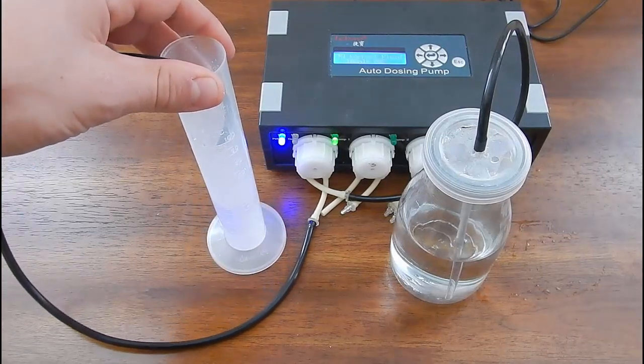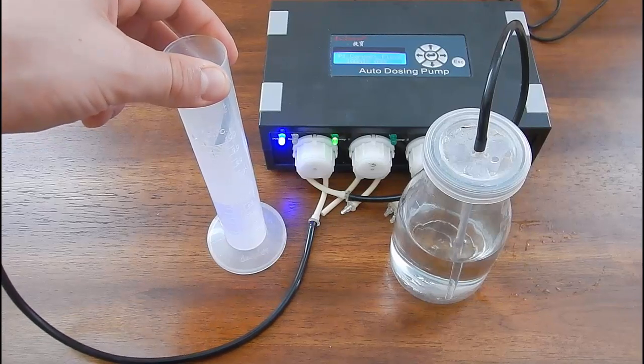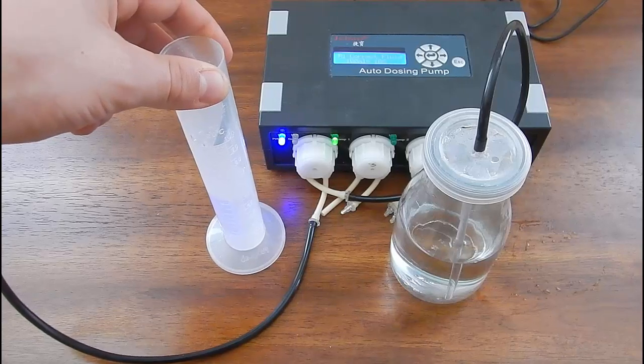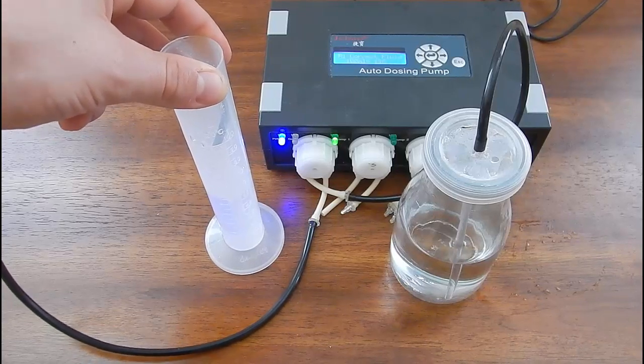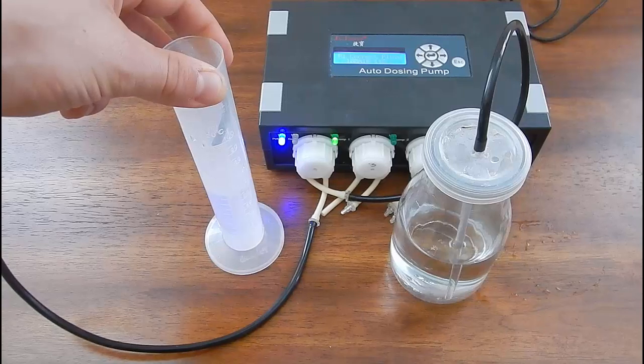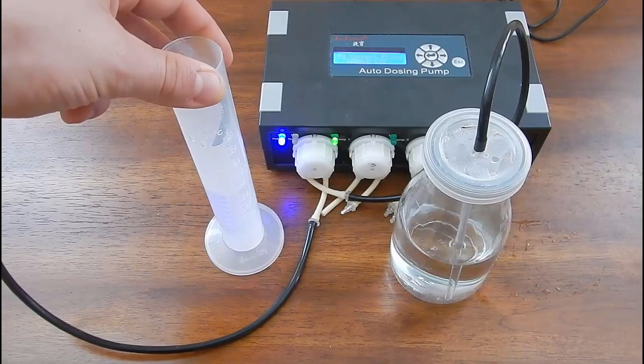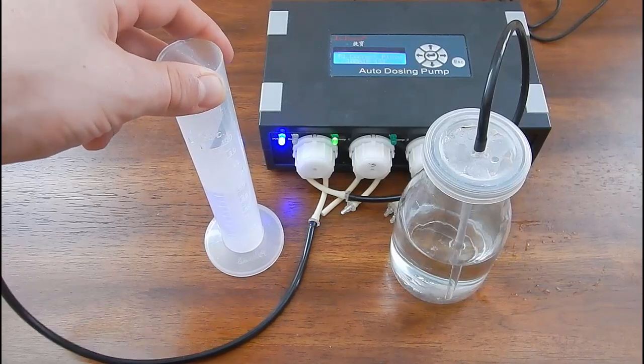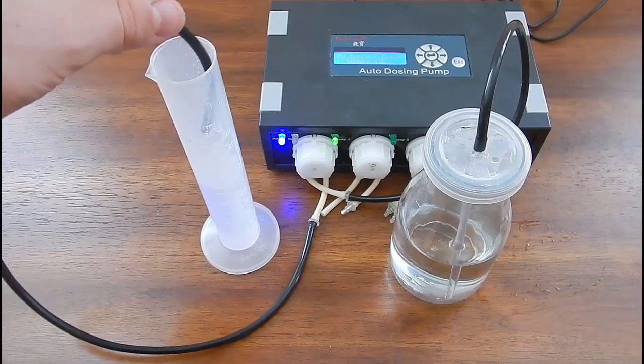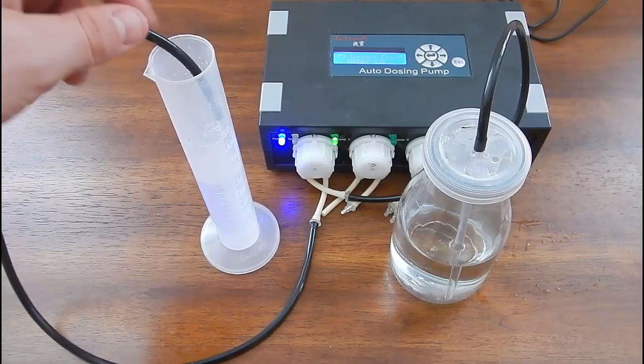Now, when it comes to calibrating, I usually calibrate every 8 months or so. It just depends. If I notice my alkalinity is getting used up a little bit more out of the reservoir, it's kind of an indication the pump might not be calibrated right anymore. There might be a blockage in the line, or it might be dirty. Then you want to go through and recalibrate the pump. It doesn't hurt anyways.